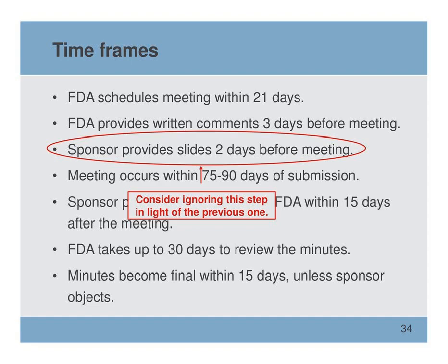Back to that time frames. Hey, FDA says that they want the slides 2 days before the meeting. I would kindly advise ignoring this step. And here's why. Because 3 days before the meeting, you've gotten FDA's written comments, and they're usually extensive. And you're going to spend quite a bit of time reacting to those comments and discussing them internally and trying to figure out strategy and where did we go wrong or something like this. You're not really going to have time to suddenly finalize your slides. I hope you're working on the slides before that time, but trying to finalize your slides, not very helpful.